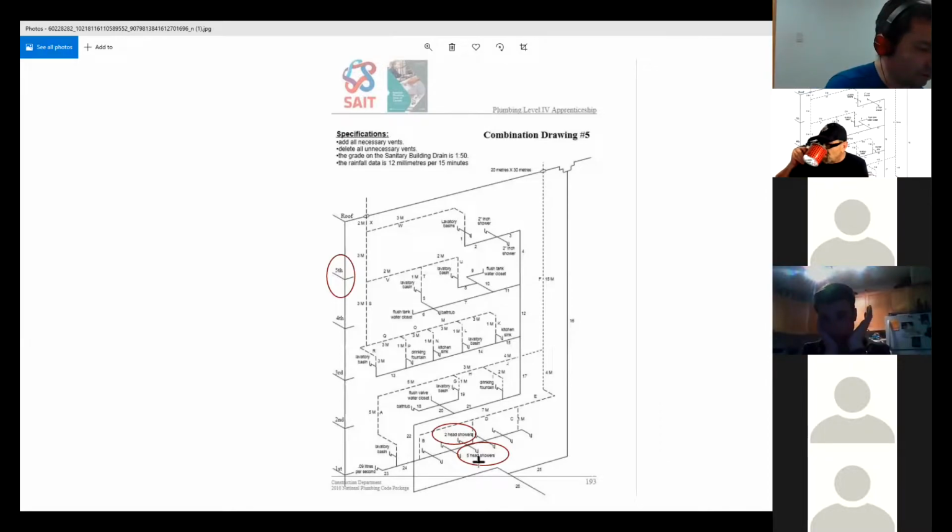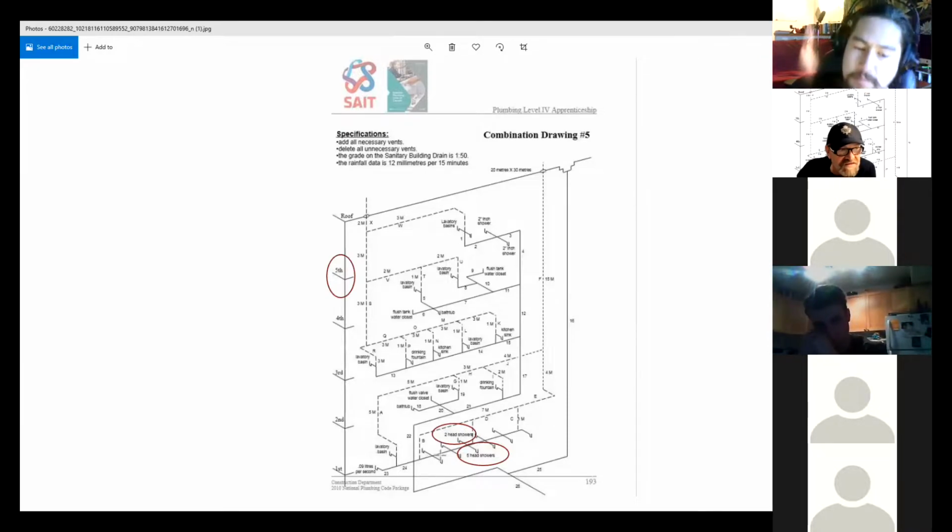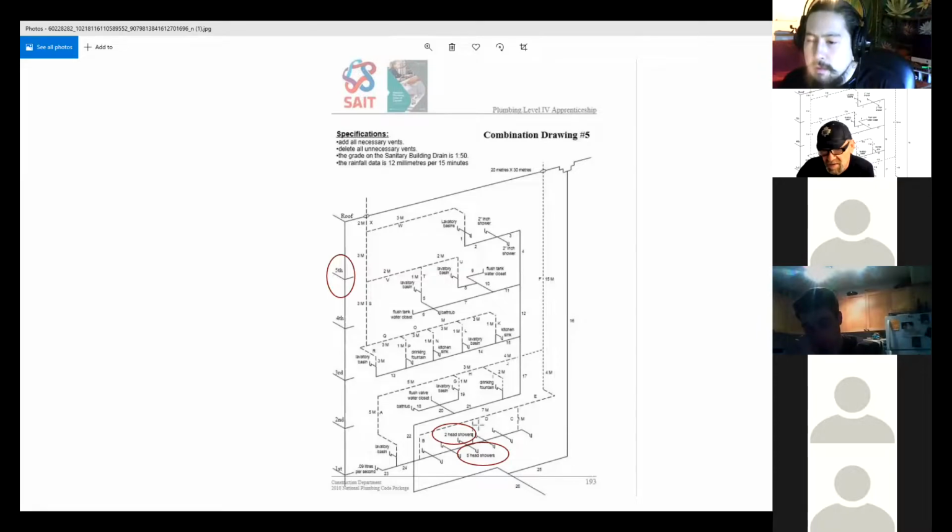6. I think it's 6. Are you reading it right from the table? Yeah, 6. And how much is a 2-headed shower? 3 fixture units, right? Well, look how many. We obviously have exceeded 8 fixture units from this branch. So there's no way in the world this could be the vent stack, right? Because you can only dump 8 fixture units.